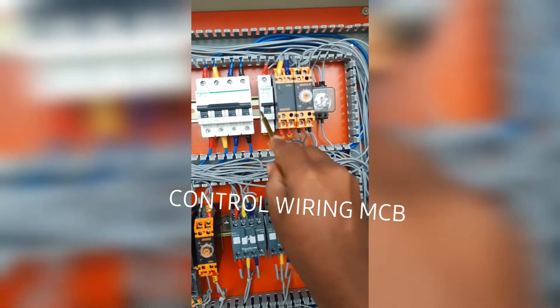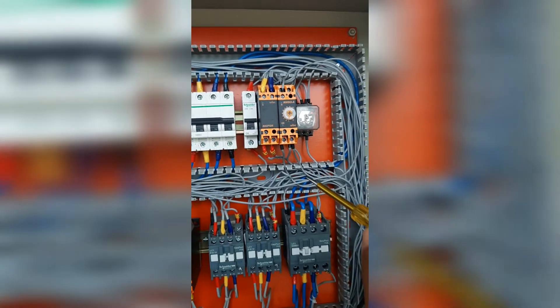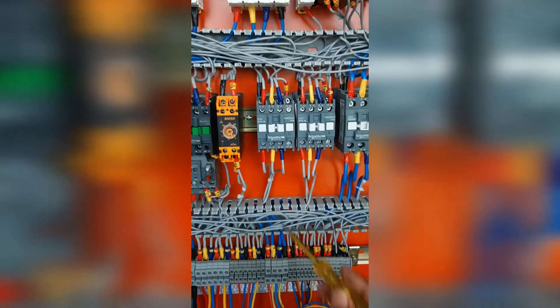This is the vane MCB and defrost MCB. Control panel MCB, single phase preventer. These are relay and timer, delay timer. Next is compressor contactor with OLR — overload relay. This is star delta timer, condenser fan contactor, evaporator fan contactor, defrost contactor.